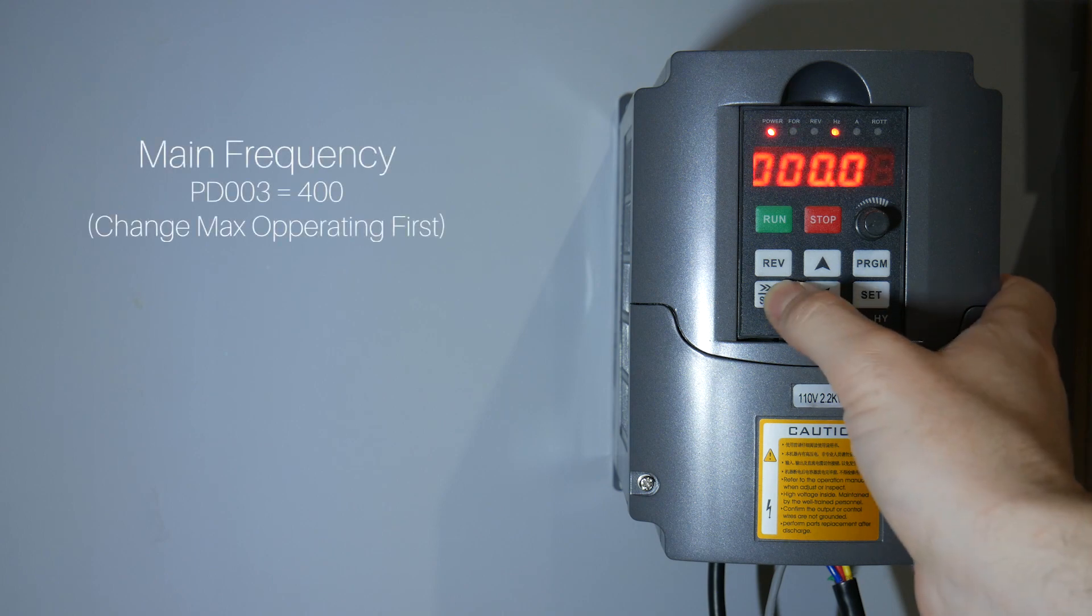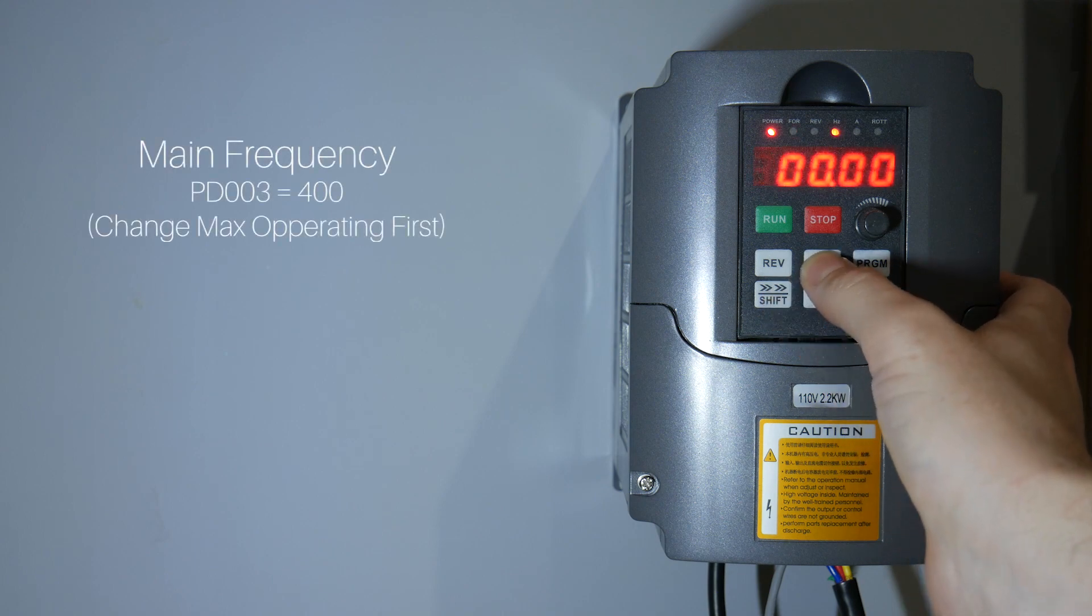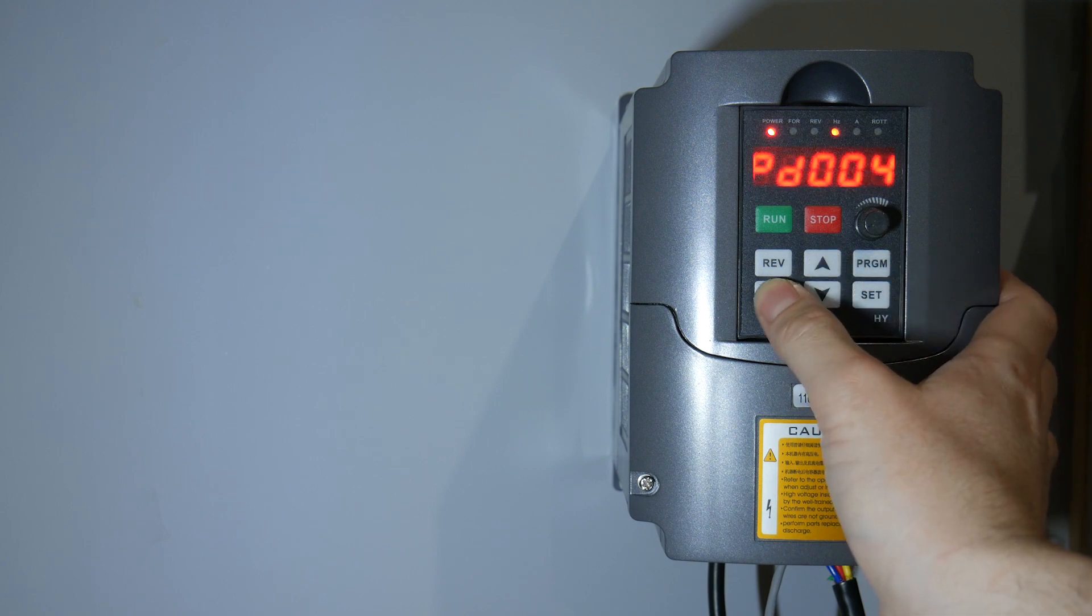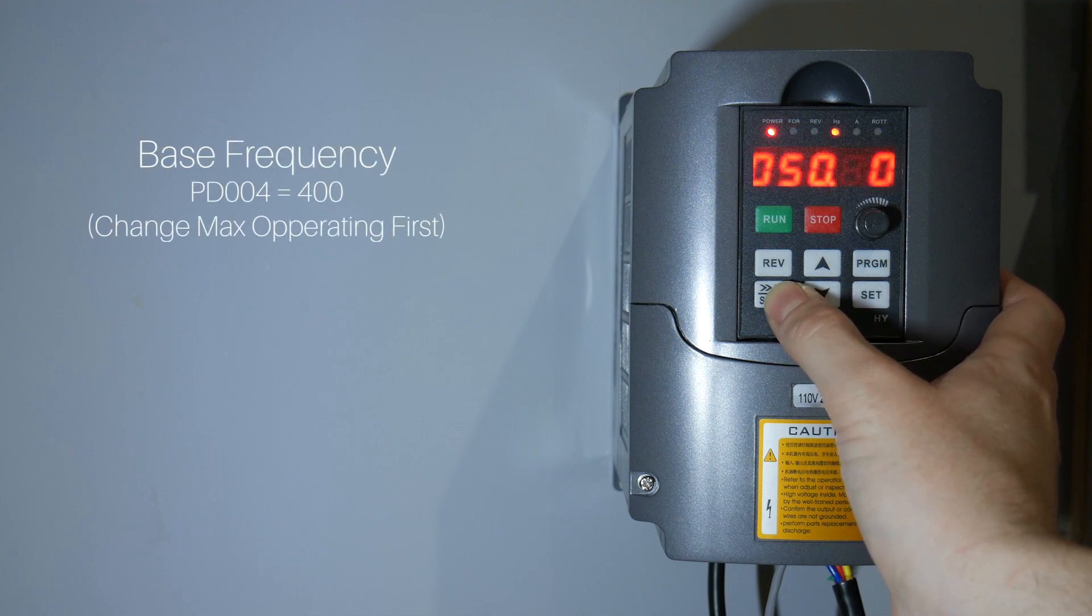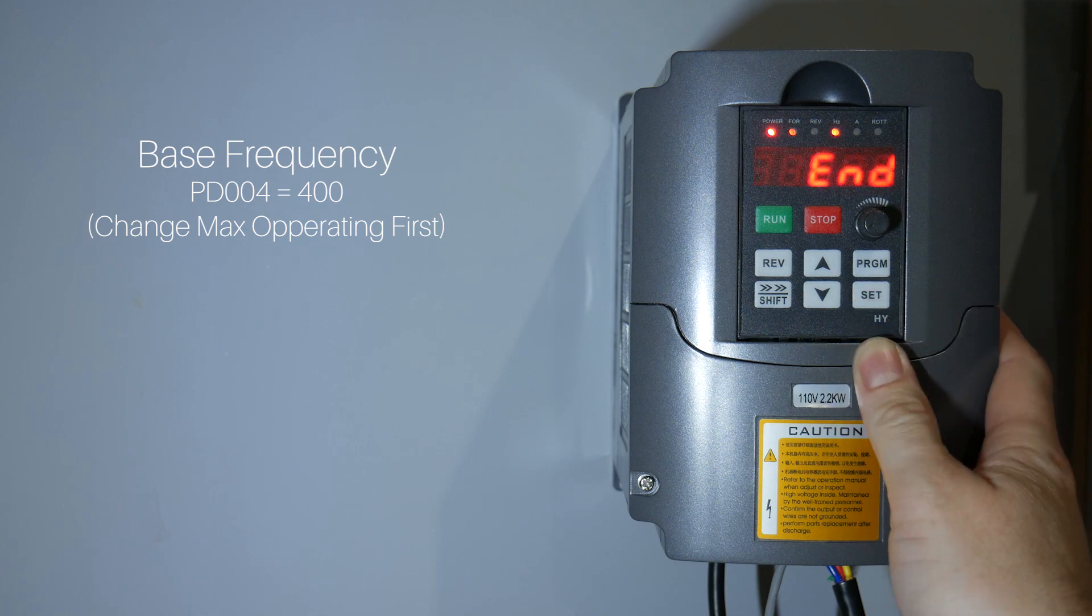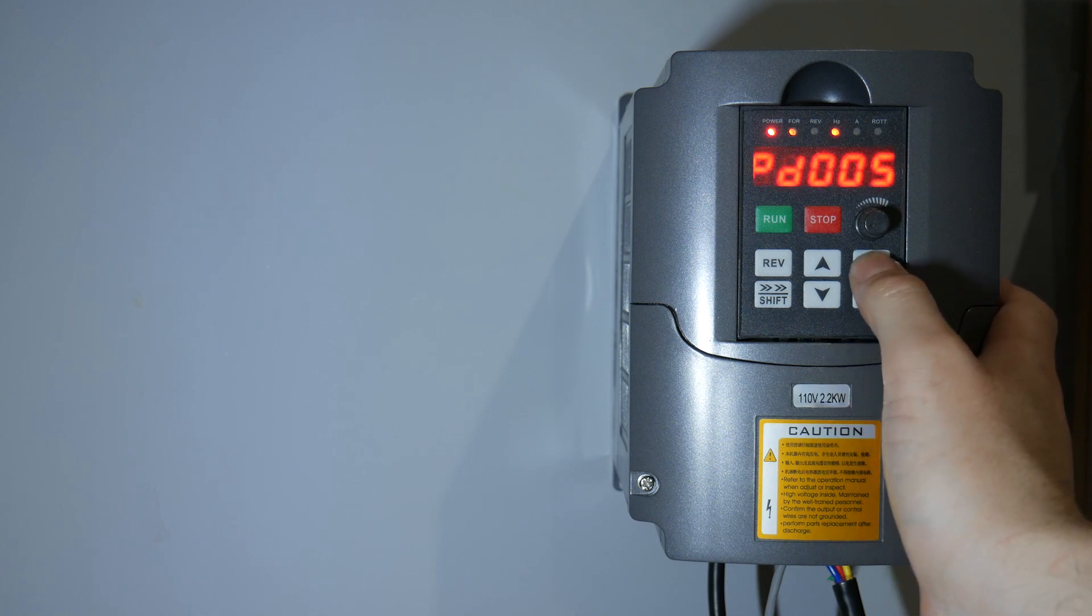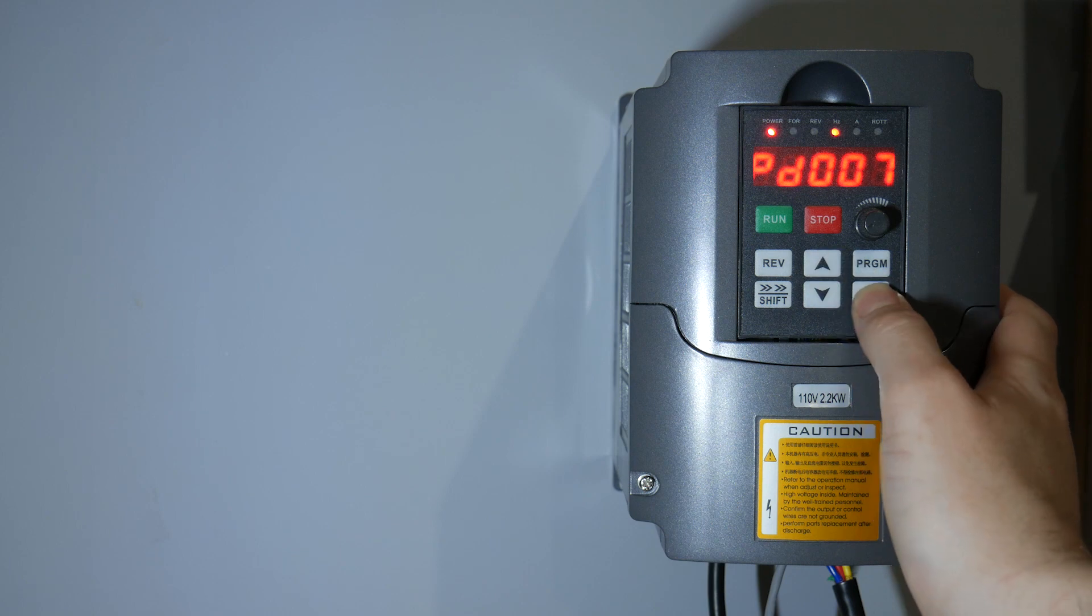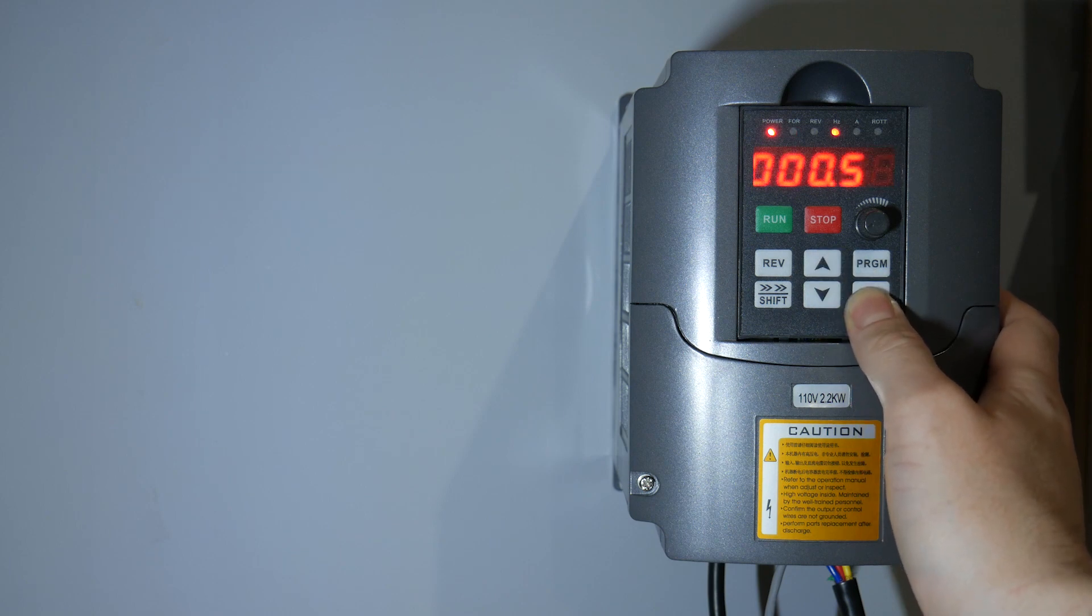Let's go back to our main frequency. Now we should be able to set this at 400. Base frequency should be set to 400. And our min frequency should be 0.5.